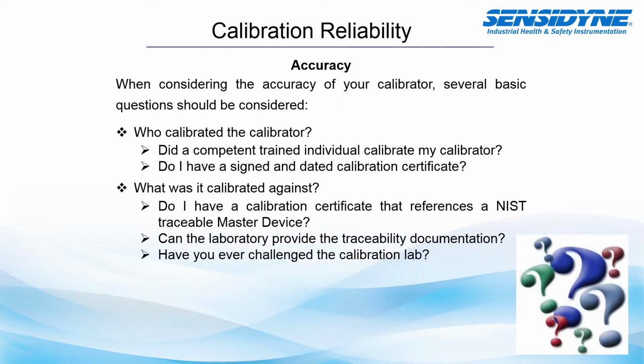So when considering the accuracy of your calibrator, several basic questions should be considered. Who calibrated the calibrator? Was it calibrated by a competent, trained individual? Do I have a signed and dated calibration certificate? What was my calibrator calibrated against? Do I have a calibration certificate that references a NIST traceable master device? Can the laboratory provide the traceability documentation if requested? And then really think, have I ever challenged the calibration lab to ensure that they actually are using traceable measurements?